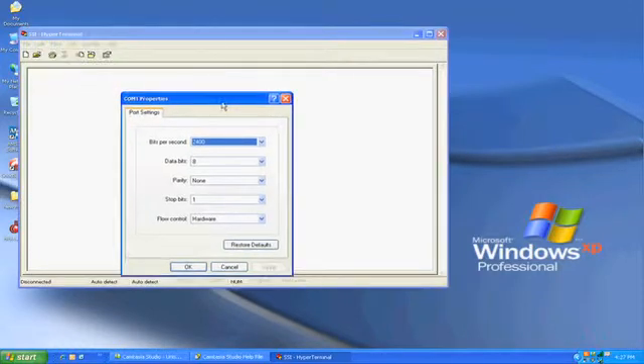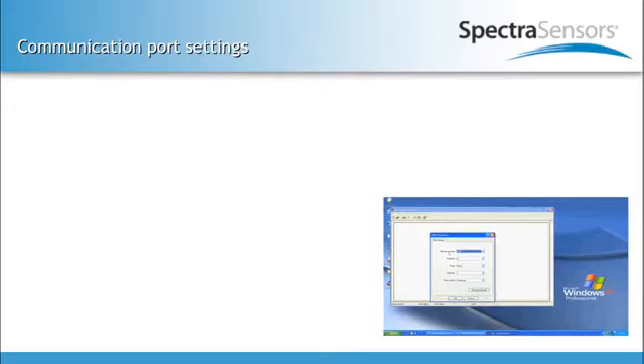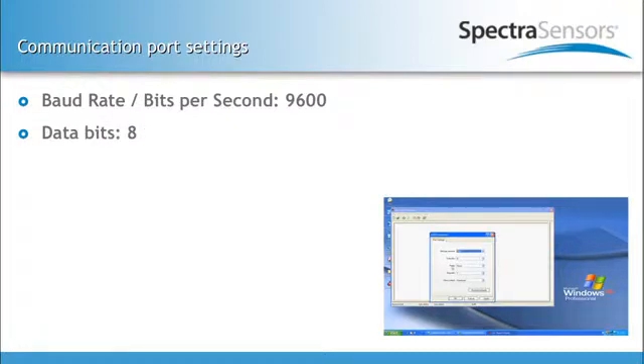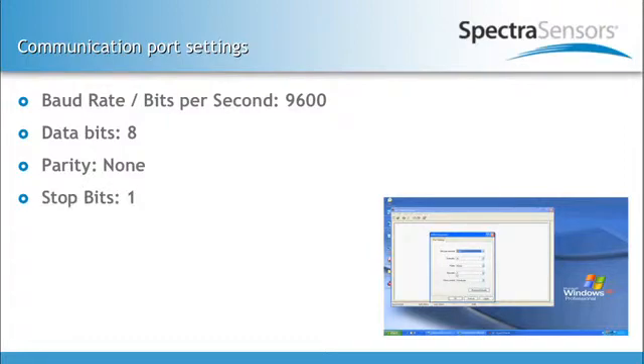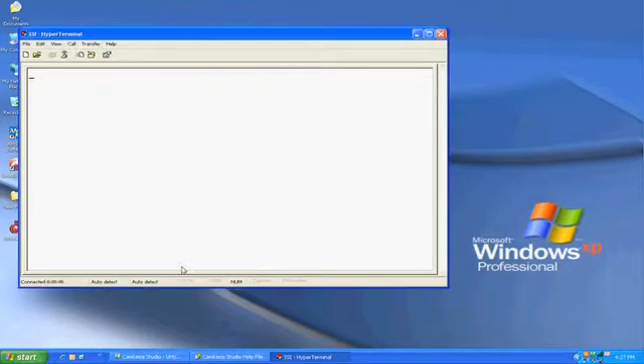Next, it will prompt you for your COM1 properties. You enter the following data. Bit per second would be 9600. You would leave the data bit as 8. You would leave the parity bit as None. The stop bit as 1. The flow control, you would change that to None. You press OK.